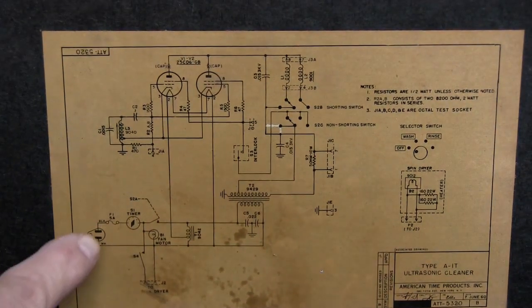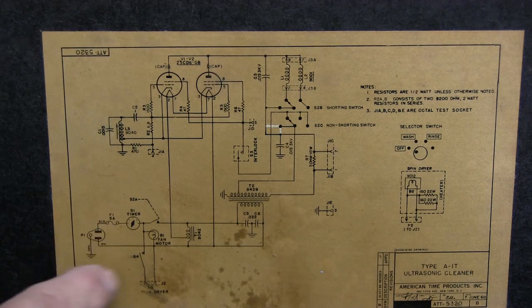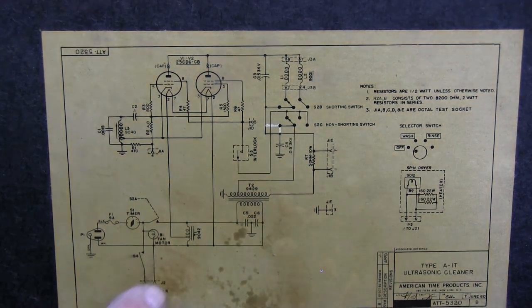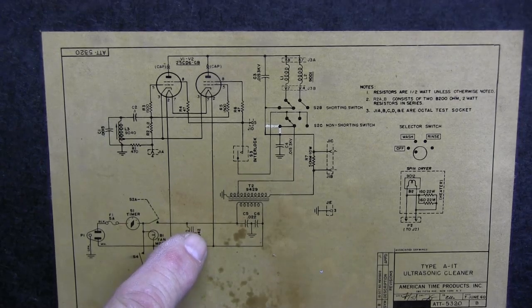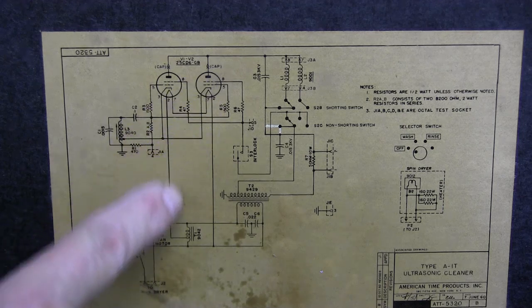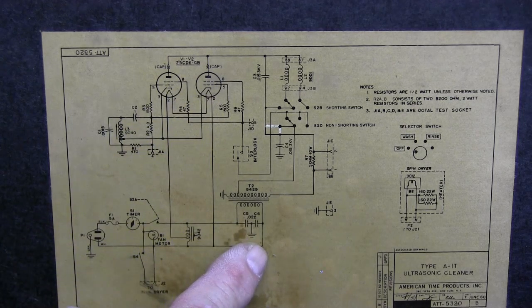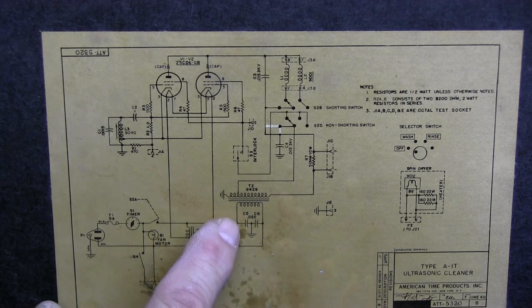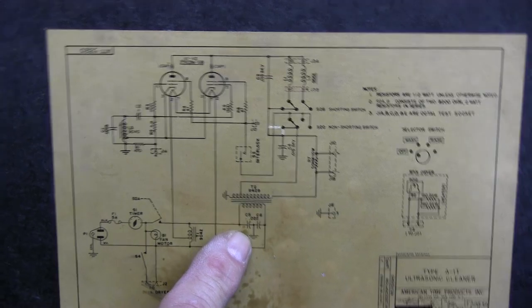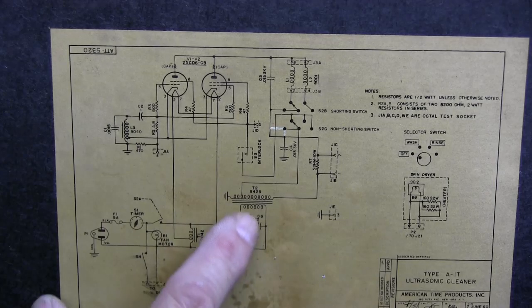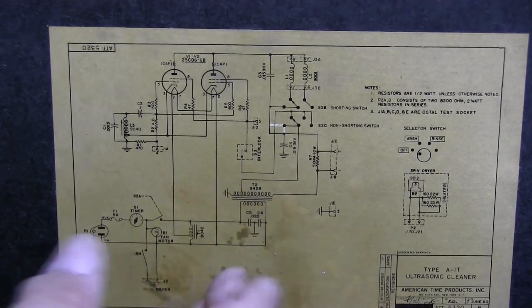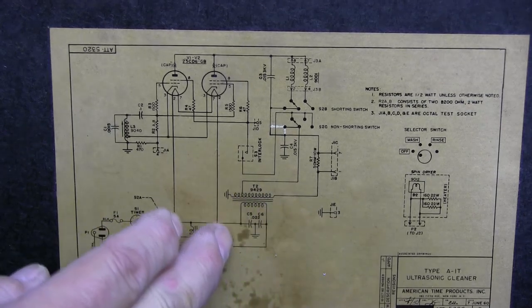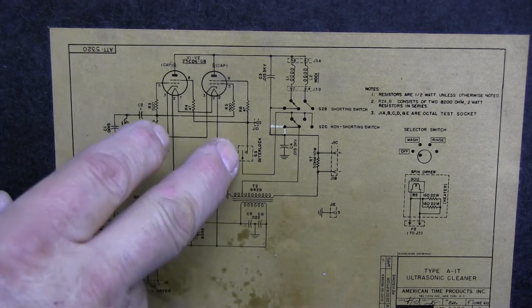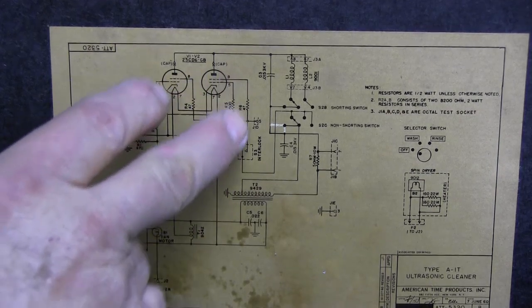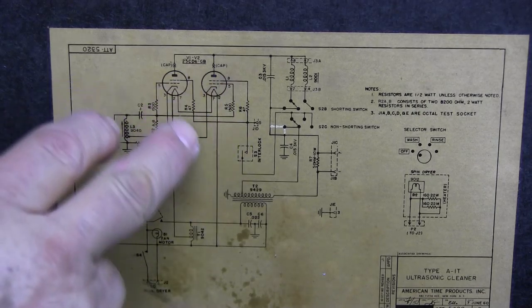So as you look at this, there's your AC plug coming in, goes through a 5 amp fuse through the timer. There's a fan that just goes off to the dryer unit, and we've got another transformer for the filament, and the filament comes up and runs in series through both tubes and comes back. So that's probably like a 50-volt transformer. Then we've got two capacitors here on either side of the line cord, and these are 0.022 at 3 kilovolt. Then you have your transformer, and what you do not see is any rectification in this. We have an interlock switch, and that goes on up to one of the grids of the tubes. It splits off here.